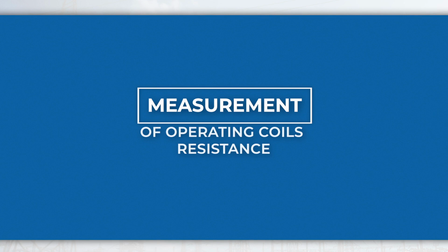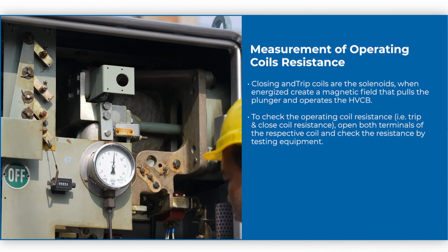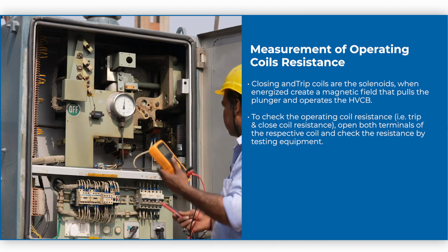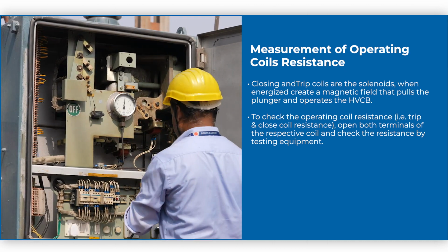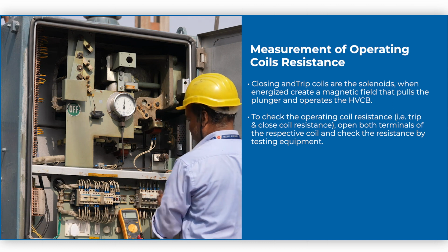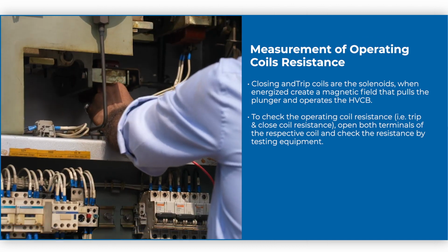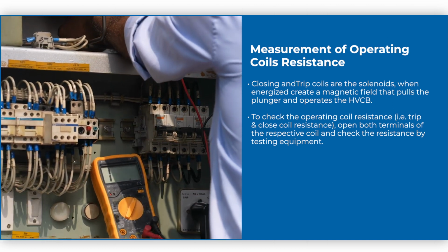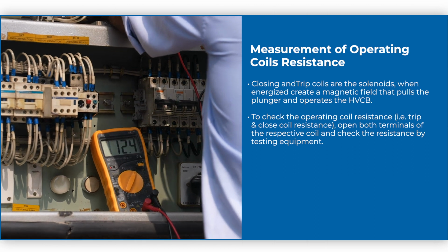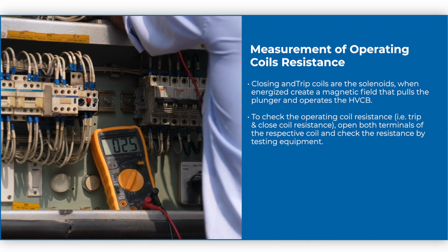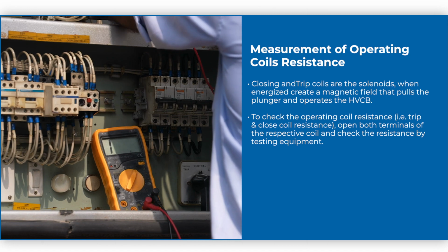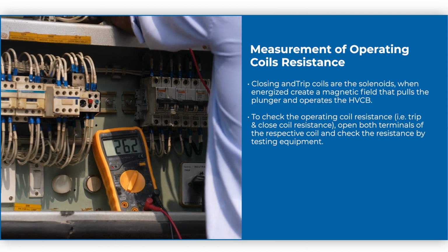Measurement of operating coils resistance. Closing and trip coils are solenoids that, when energized, create a magnetic field that pulls the plunger and operates the HVCB. To check the operating coil resistance, that is, trip and close coil resistance, open both terminals of the respective coil and check the resistance by testing equipment.